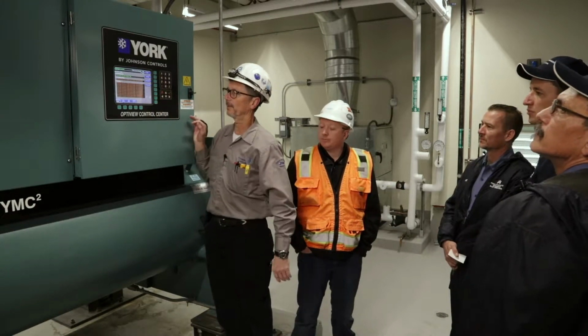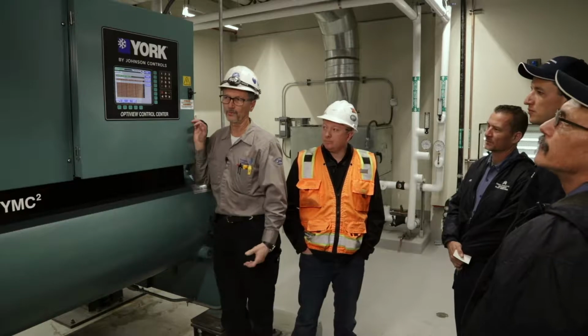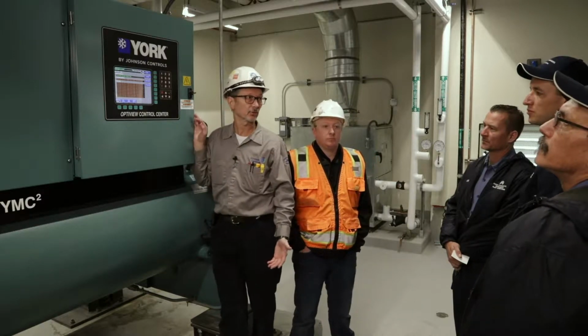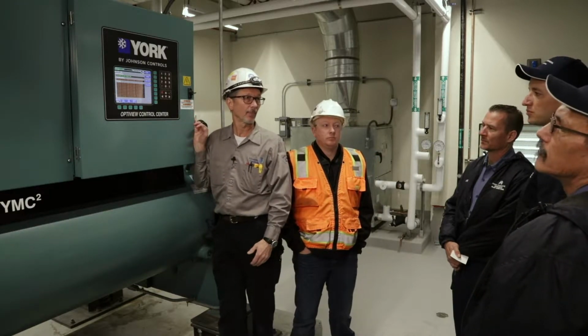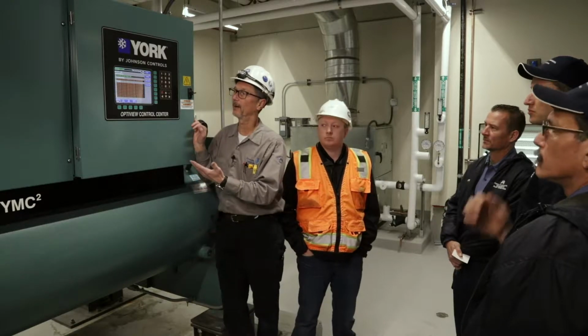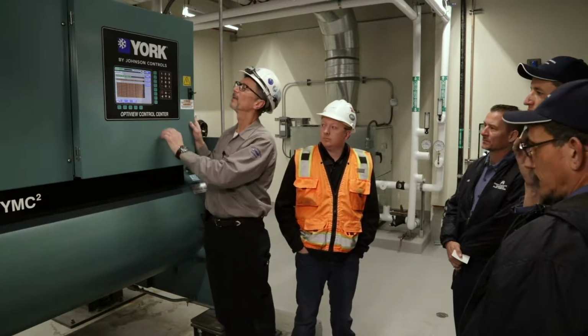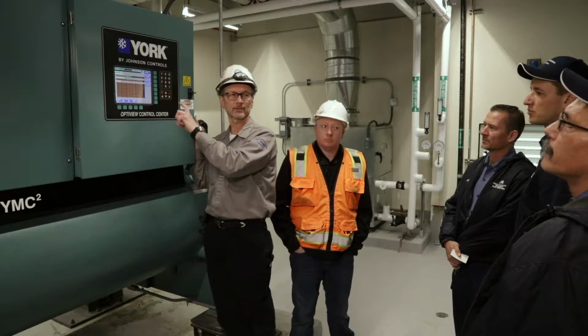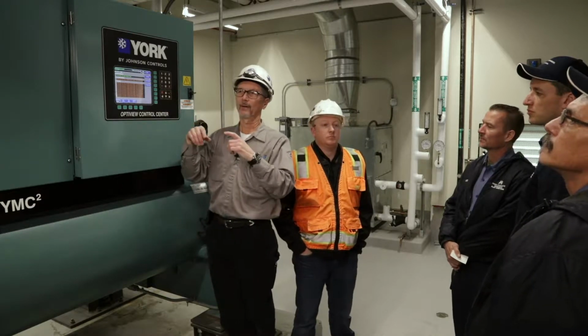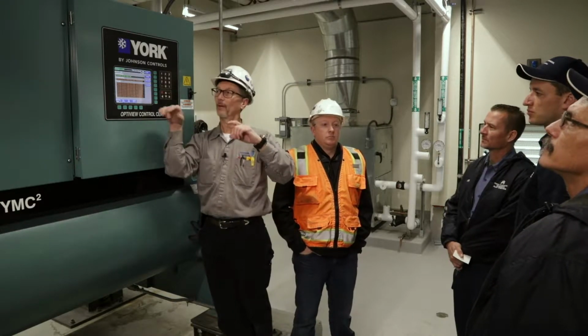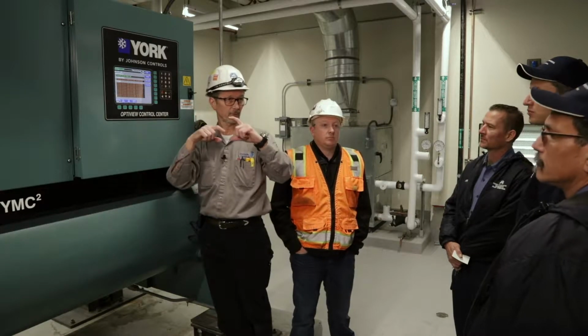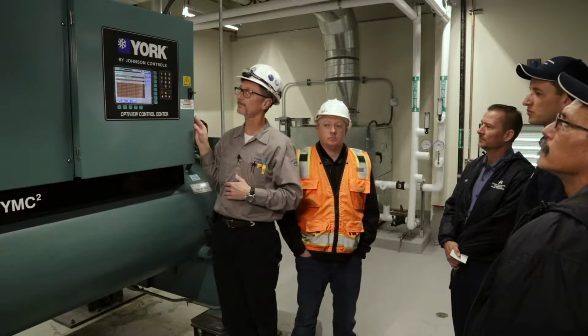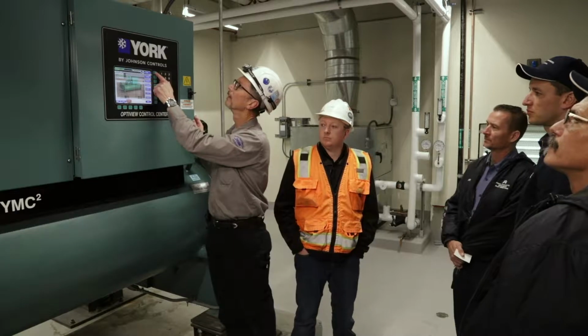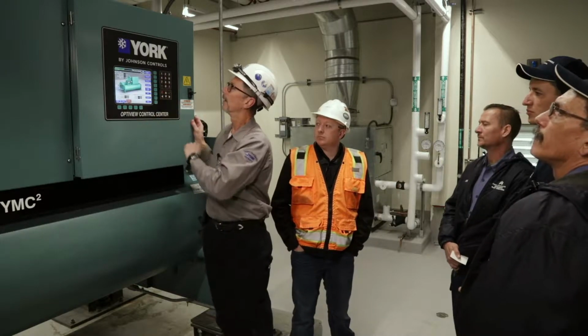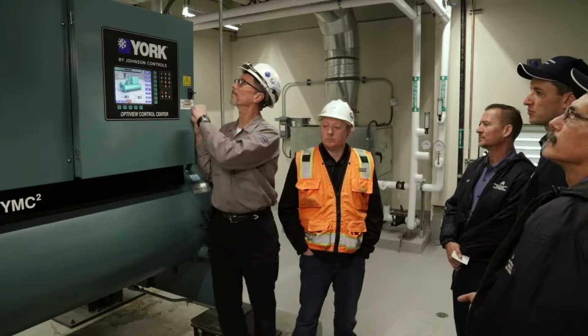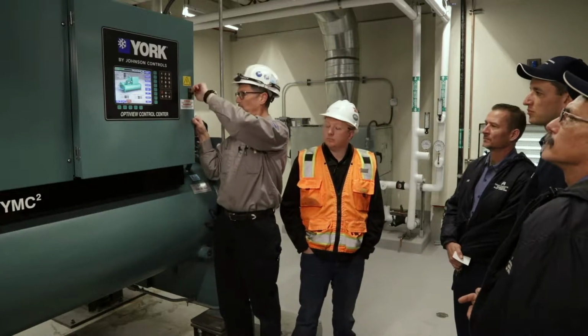And then history. History will be one of the most important ones. If you're going to walk up to this machine because there's a problem, typically, is why you're having to check it. And go to the history, and you can see the last 10 faults in here. After the 11th fault comes up, the last one on the bottom drops off, and then it just keeps scrolling down. You can only save 10. I'd like to show you the inside of the control panel now.